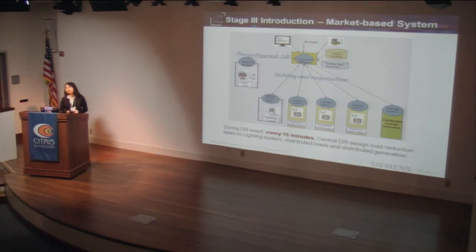The lighting system and the plug loads have a feature, which means that they can react in real time, and their power reduction corresponds directly to your control command, which means I turn off a light, I shed 60 watts. And that's not the case for the HVAC. That's why we want to put those systems together to contribute to those portions that the HVAC cannot meet when we are doing all the pre-configurations, pre-optimization. And we can do that in real time.